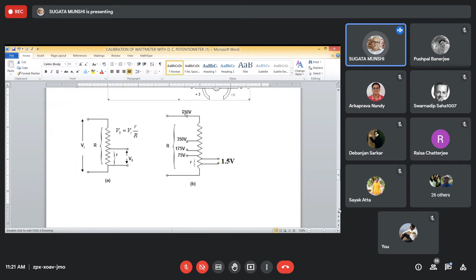We will use that. Now coming back to the wattmeter, what is meant by calibration of the wattmeter? The wattmeter has a scale, and you want to find out whether the graduations on the scale are correct or not, or what are the measurement errors at salient, marked points on the wattmeter scale. The wattmeter considered here has a basic range of 0 to 100 watts. There can be multipliers on this 0 to 100 watt range. So there are graduations, markings of 10 watt, 20 watt, 30 watt, and so on.